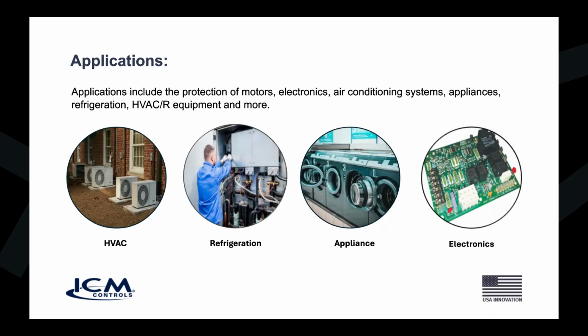So some applications that we see these used in are HVAC equipment, a lot of your mini splits, protecting mini splits, HVAC equipment, air conditioners, rooftop air conditioners, residential air conditioners. You can protect your heating equipment, furnaces, anything that's single phase 120 or 240 volts for the 517A and 517A Lite models in our single phase lineup. Also, we see these in refrigeration applications to protect sensitive electronics and refrigeration units from those surges.